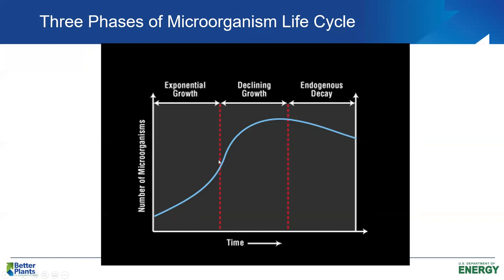As we move along the growth curve, food becomes less available and growth rate falls off — we call this the declining growth phase. This is generally where we get our best settling activated sludge, a good distribution of microorganisms, and probably our best settling sludge. As we continue into extended aeration, we enter endogenous decay: most food has been used up and microorganisms are feeding on themselves — endogenous respiration — oxidizing their own protoplasm to generate energy to stay alive.